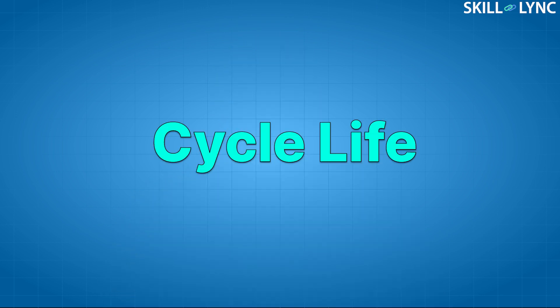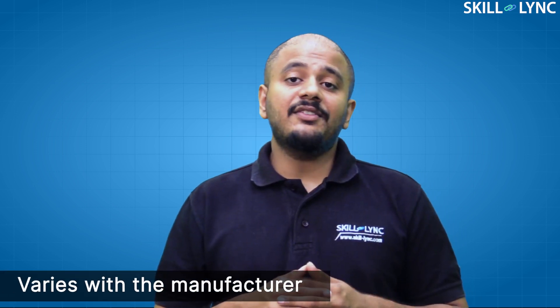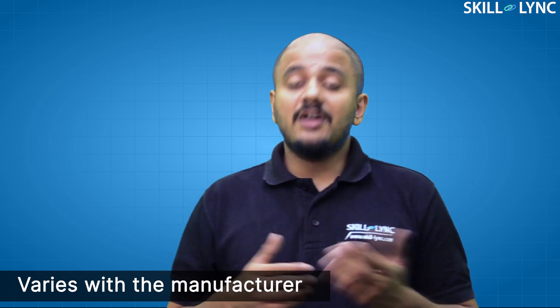The next parameter for comparison is cycle life. Battery life is specified in terms of charge-discharge cycles; one cycle consists of charging the battery to its full level and then discharging it to the minimum permissible lower limit. Lead-acid batteries tend to have a life of around 300 cycles with a depth of discharge of 50 percent. This means by the time the battery undergoes 300 charge cycles, the capacity would be reduced to 50 percent of its original value.